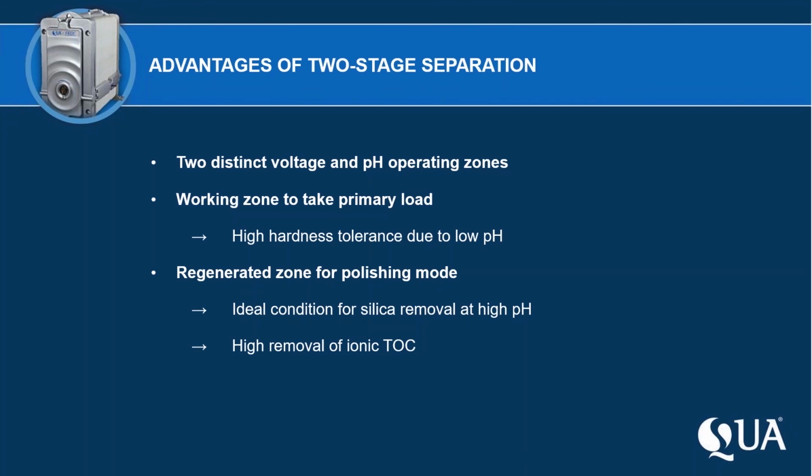Very robust system, used the same principles, but it would never be used in a high purity water application because you'd never want it to split water, because that's where the scaling would occur. You'd have these higher pH regimes mixing with some of your divalents and maybe some alkalinity, and that's what forms scale. So the beauty of the EDI is having these two distinct voltages and pH operating zones: the working zone taking the primary load, the regeneration zone, the polishing.